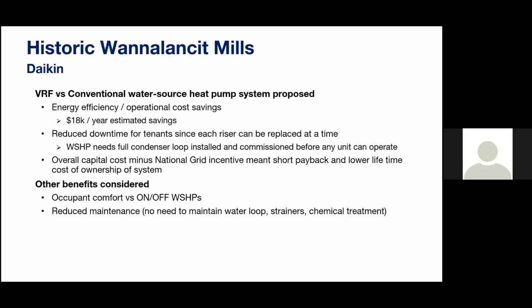The downtime for the tenants in going with one water loop that would need to be up and running prior to operating any of the water source heat pumps. So this, of course, would add significant downtime to not have proper heating or cooling system, rather than just using temp heat or temporary fans. So that was a big deal with going the VRF route. And then with all the incentives nowadays for going all electric, the capital cost of the VRF system allows for short payback and lower lifetime cost of the system.